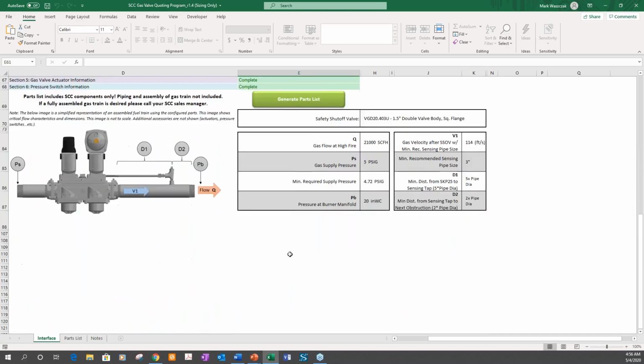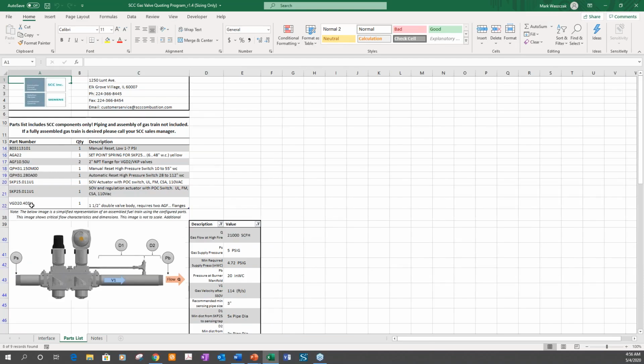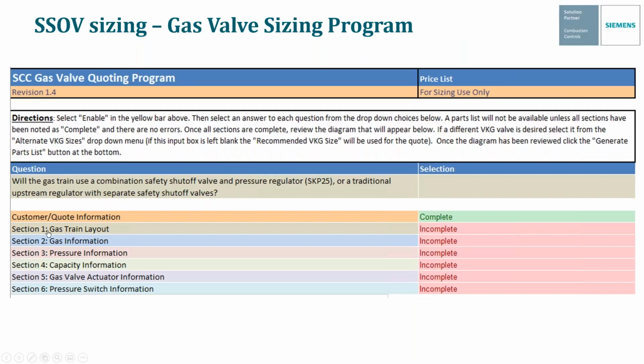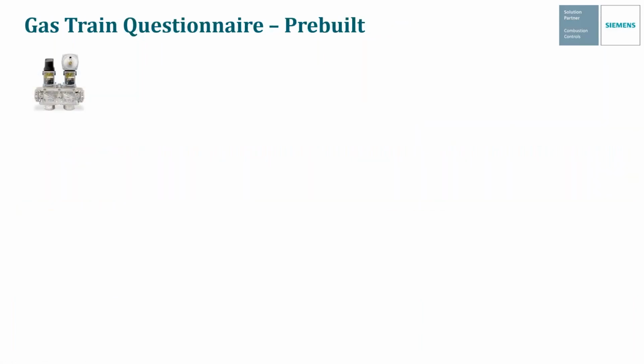Once all that is done, you could go onto this generate parts list and click on it. What it will do is select all the parts that are required for this gas train. As you will notice, for this size boiler, based on the conditions we put in, it did select a 1.5 inch gas valve body. This program will also be included in your handouts. Next, we're going to cover a pre-built gas train.